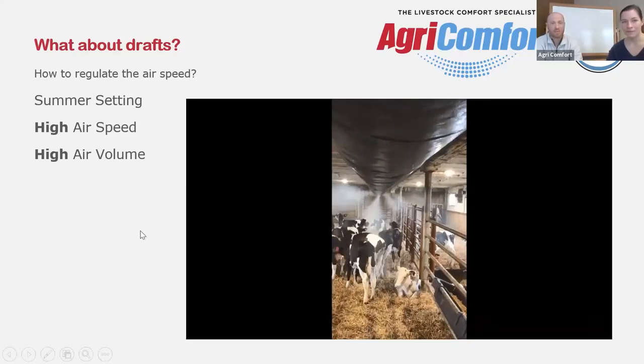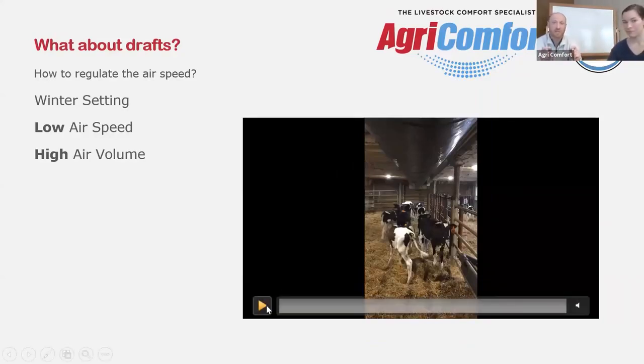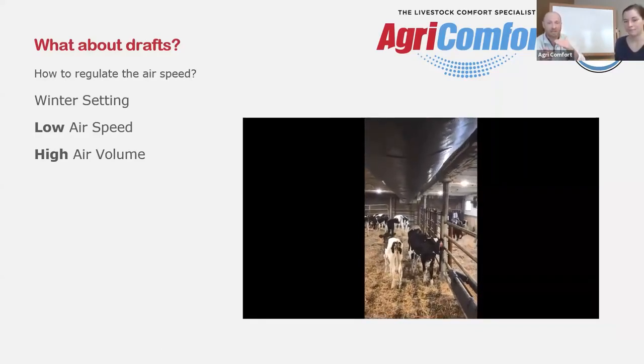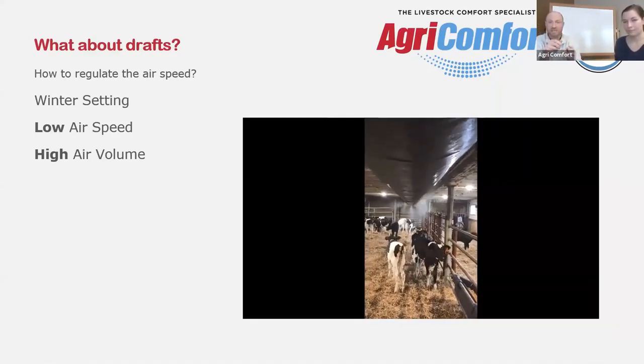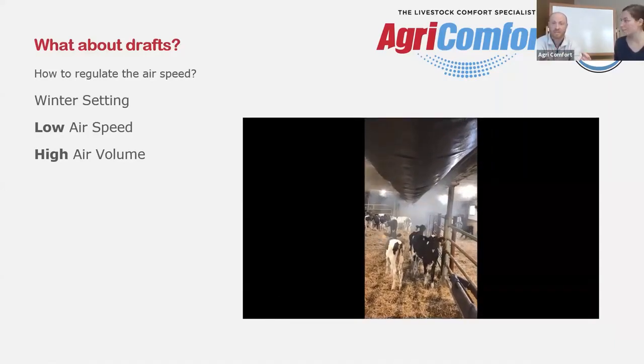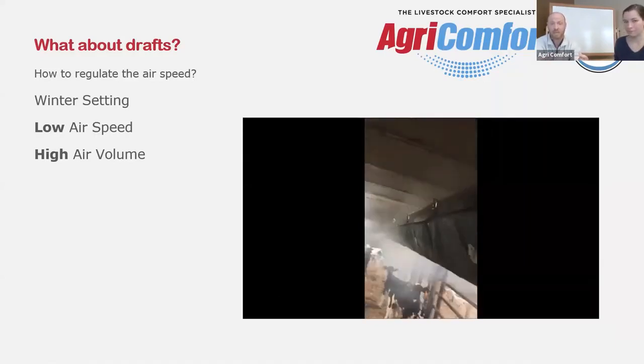So now we'll go to the next video. This is the exact same barn, the same day. And in this one, we didn't change the fan speed. So there's still 2,300 CFM coming out of this tube, but we adjusted the membrane to the bottom of the bag. We've blocked the large summer holes, and now we're letting the air out the top of the bag. And you'll see as it comes out, the video is starting to play now, that air just comes out like a gentle cloud, because we're blowing it out these little holes, and it lacks the momentum that the bigger holes had.